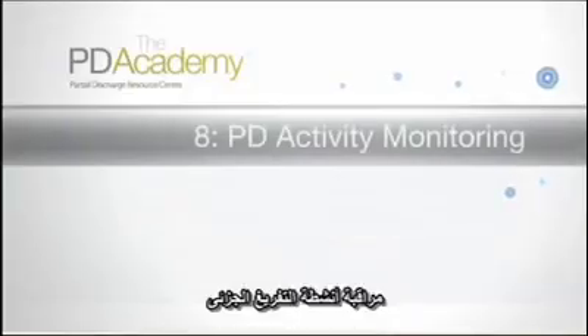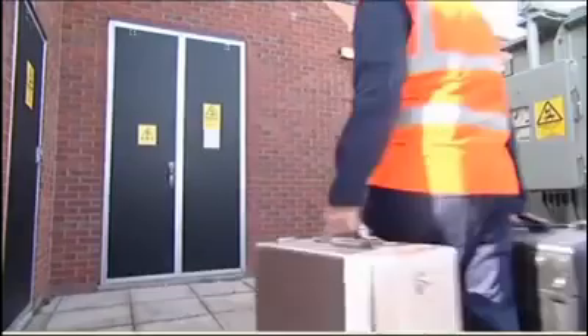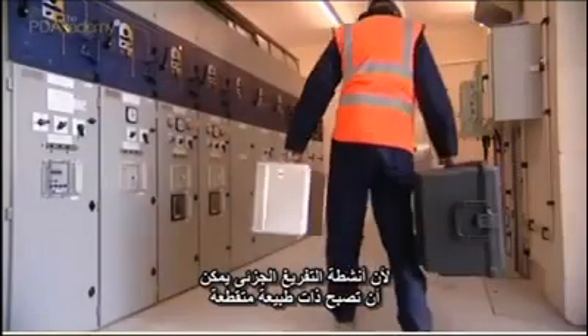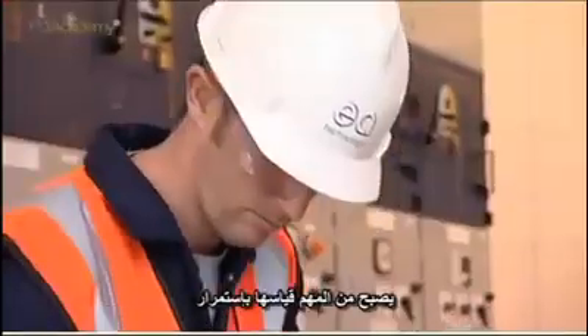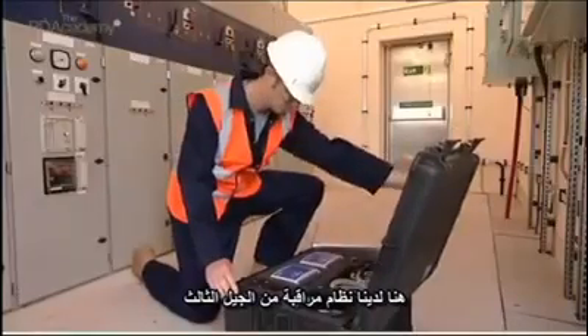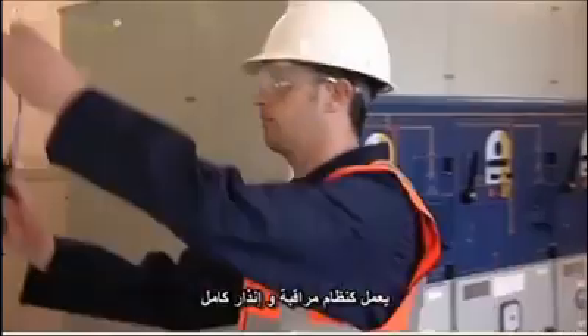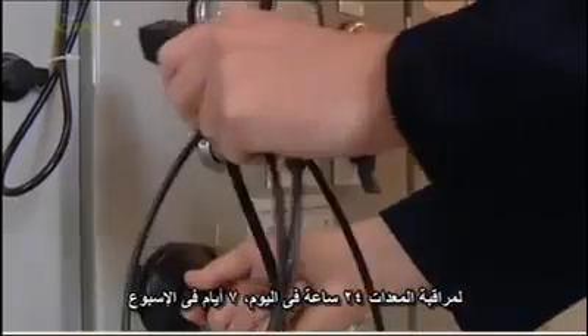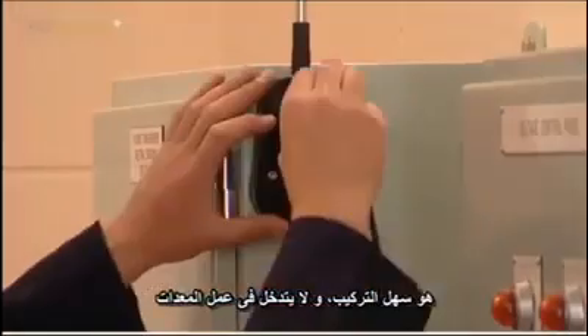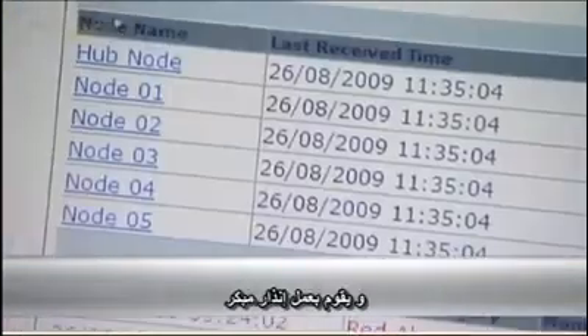PD activity monitoring. Due to the possibility of PD being intermittent in nature, it's often important to measure PD activity over time. So here we have an example of a third-generation monitoring system. It's a complete asset monitoring and alarm system for managing the condition of substation assets 24/7. It's easy to set up, non-intrusive, and works automatically without human intervention to provide continuous PD detection, location, measurement, monitoring, recording, analysis, and fault alarm warnings.